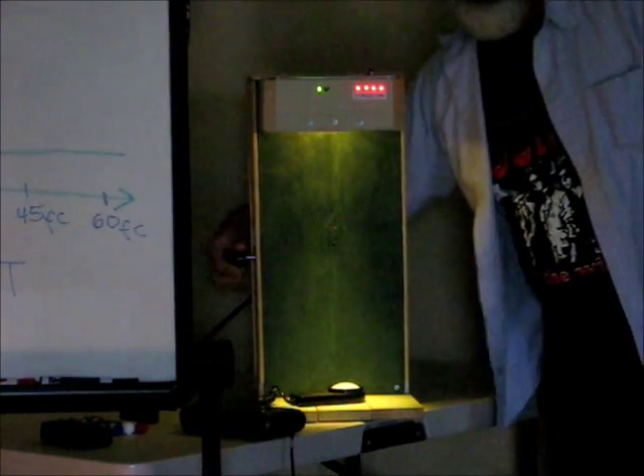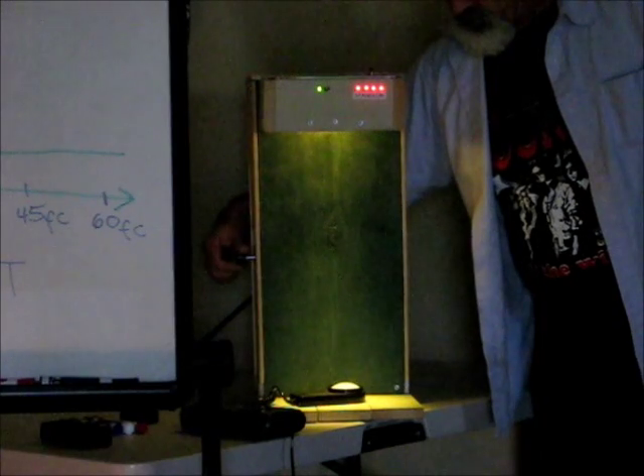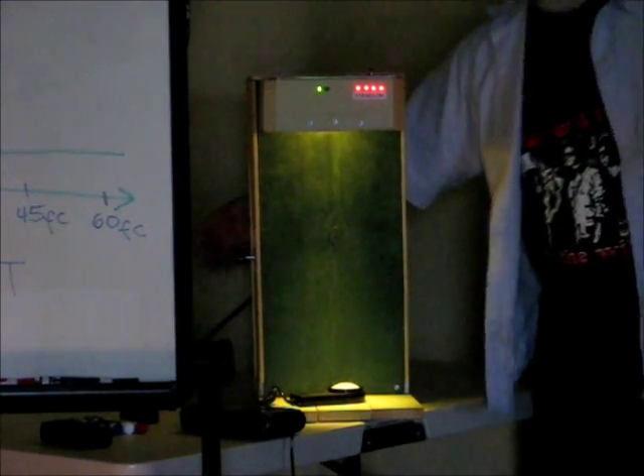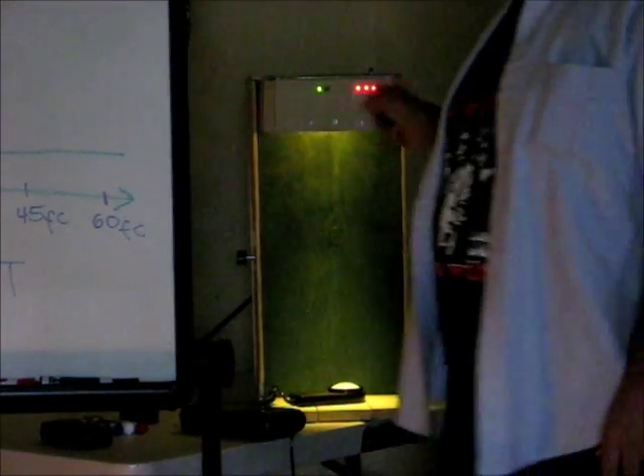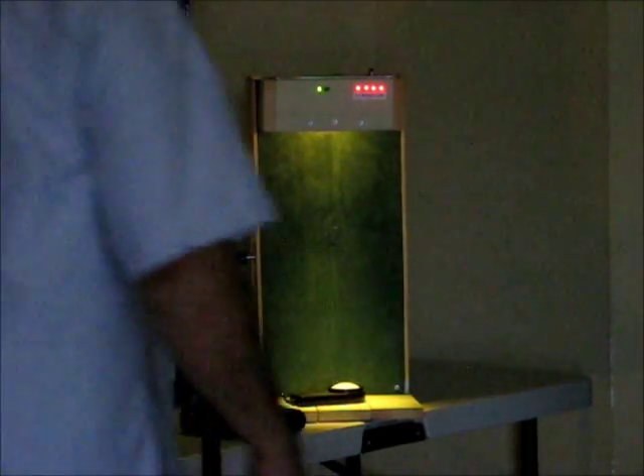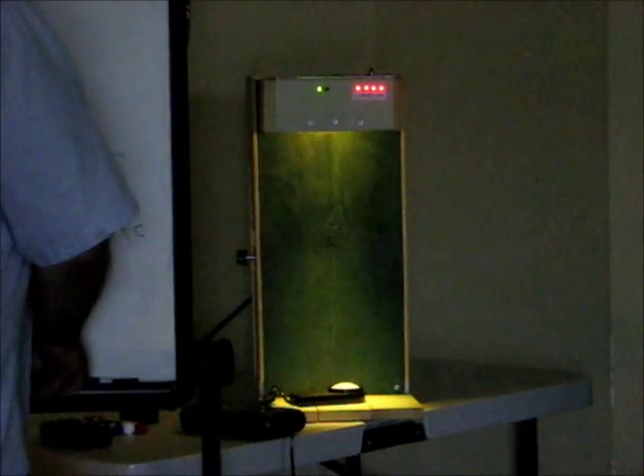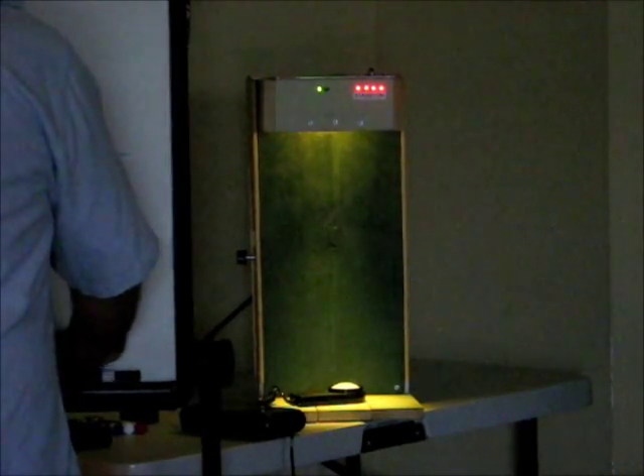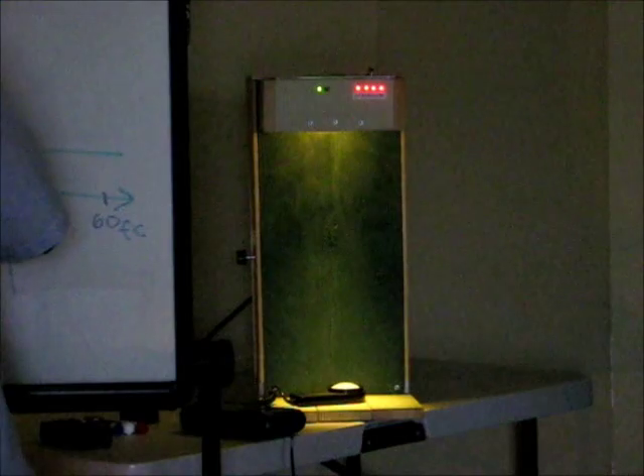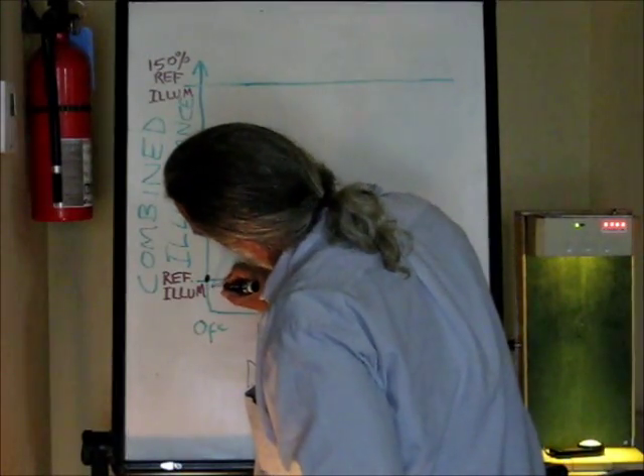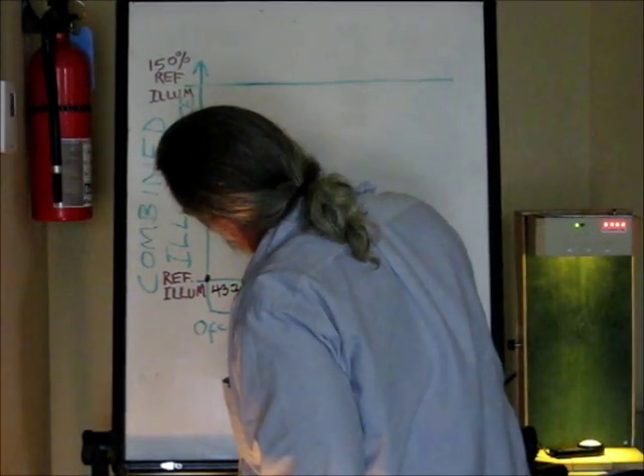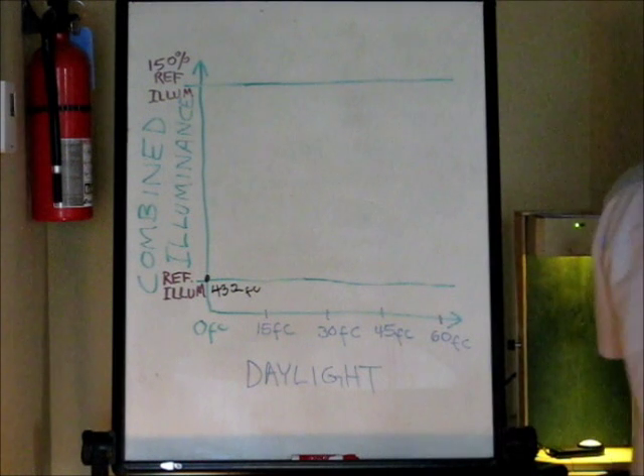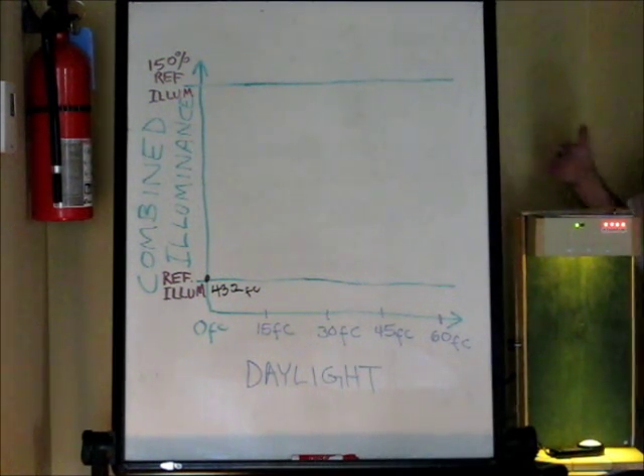Now we're under no daylight conditions. You guys will be using something just like this tomorrow. Perhaps this one. This works fine. I'll bring in a smaller one as well. We're under no daylight conditions. All four stages of the lights are on. My light meter is reading 43.2 foot candles. So that's our reference illumination. So I'm going to go ahead and put this on the chart. 43.2 foot candles under genuine no daylight conditions. That's our reference illuminance.